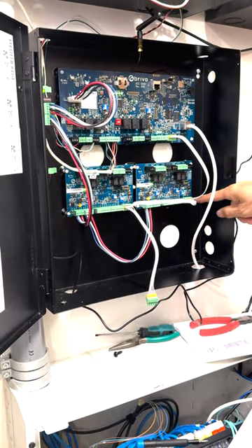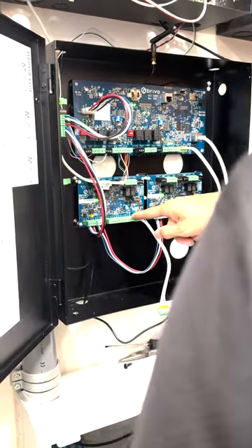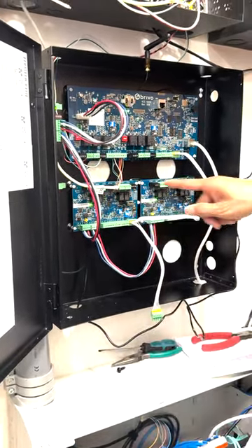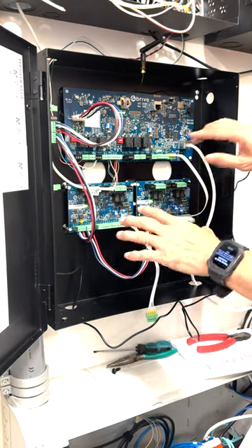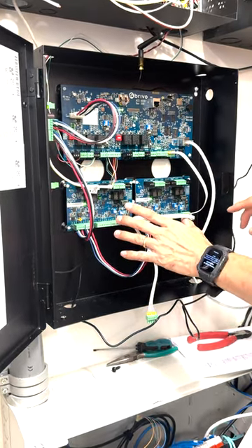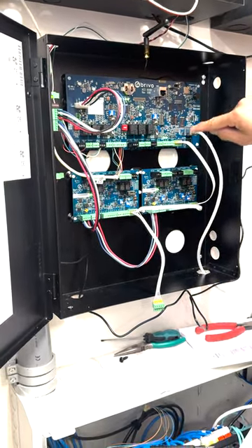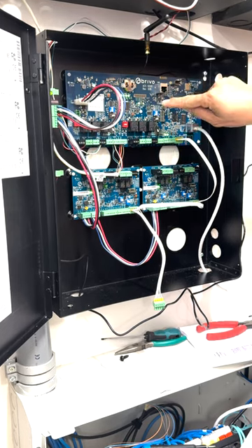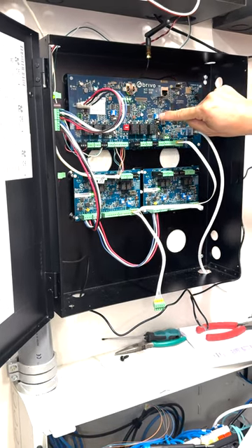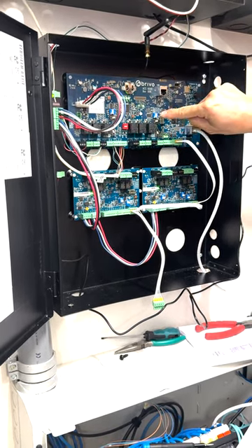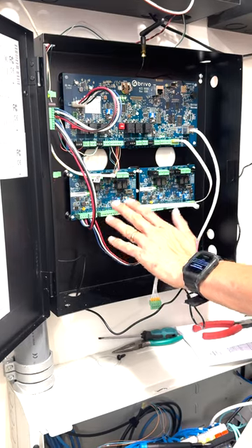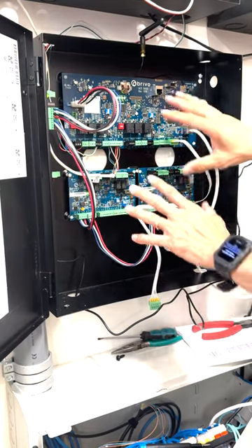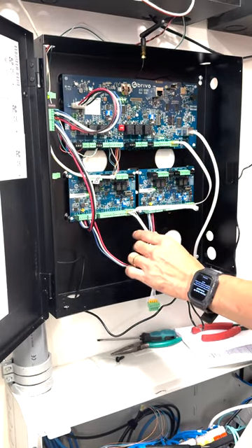Now when you install CAN bus, you want to make sure the main controller is always on at the end of the controller. So let's say if you have three controllers, the last CAN bus needs to be on, the middle needs to be off.